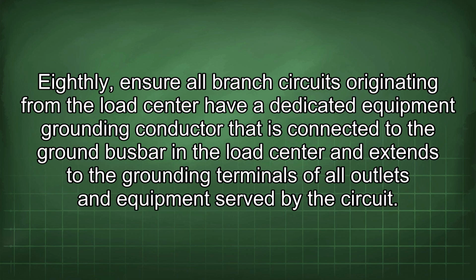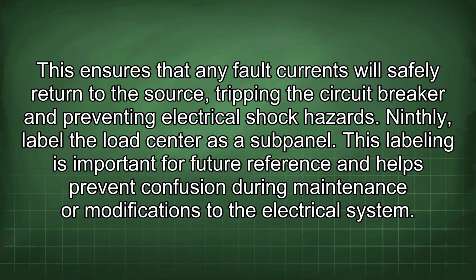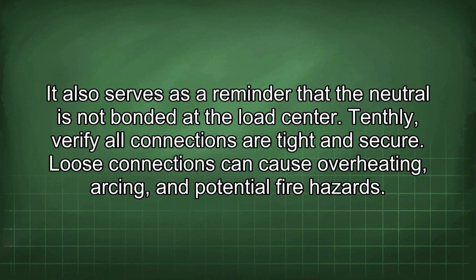Eighthly, ensure all branch circuits originating from the load center have a dedicated equipment grounding conductor that is connected to the ground busbar in the load center and extends to the grounding terminals of all outlets and equipment served by the circuit. This ensures that any fault currents will safely return to the source, tripping the circuit breaker and preventing electrical shock hazards. Ninthly, label the load center as a subpanel. This labeling is important for future reference and helps prevent confusion during maintenance or modifications to the electrical system. It also serves as a reminder that the neutral is not bonded at the load center.